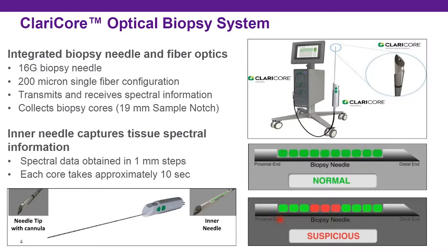Across 10 millimeters, you can see in the bottom right a depiction of how that information is displayed. Each square represents a one-millimeter advance, and red areas are indicated on the device as tissue considered suspicious, versus normal tissue shown in green. This spectral information is transmitted to the display connected to the gun and can be given as a real-time readout.